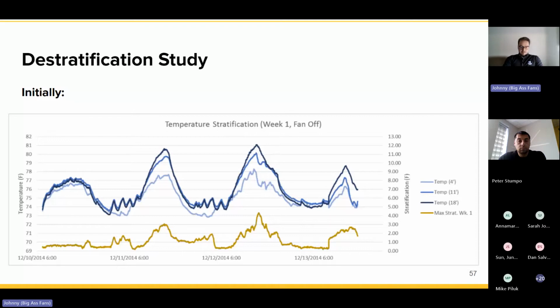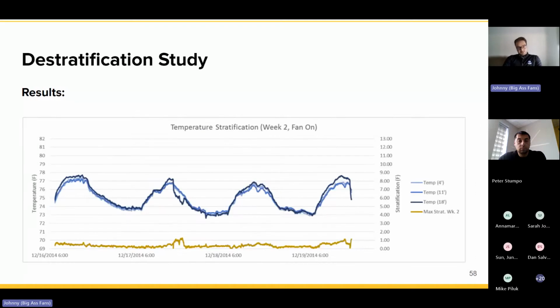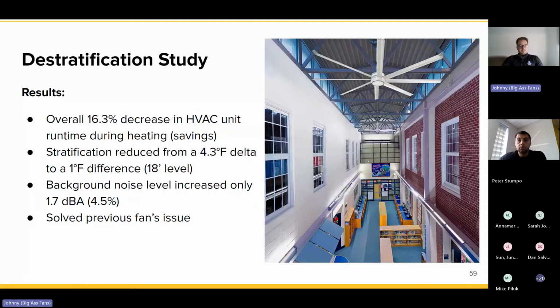As soon as we turn that fan on, like you probably guessed, we shrink that, right? You're seeing, again, a reduction to about 1 degree delta. People are comfortable, heat is kicking on less, and you have fans that are quietly and effectively mixing the air in that building. Just to summarize, we did reduce the HVAC unit runtime about 16%. We reduced that temperature delta to 1 degree, like I mentioned.